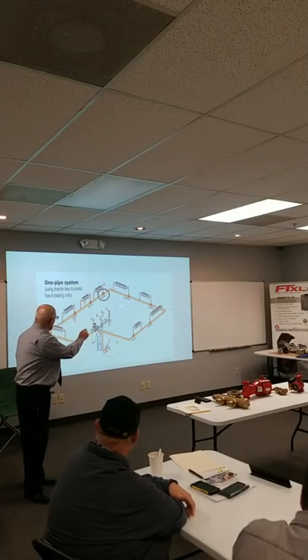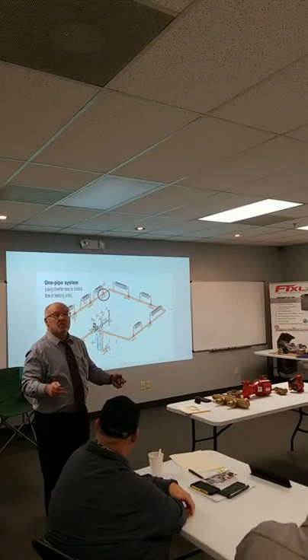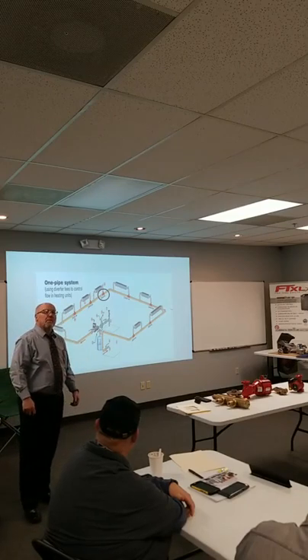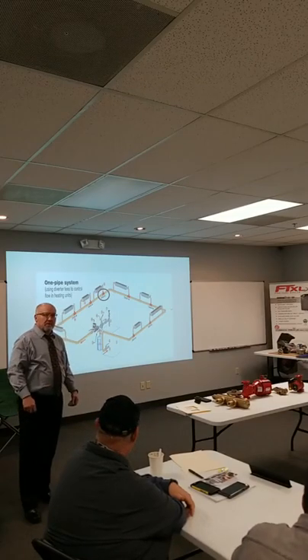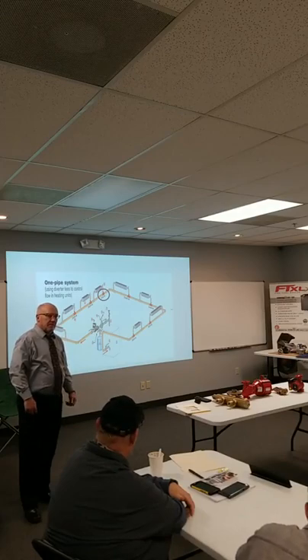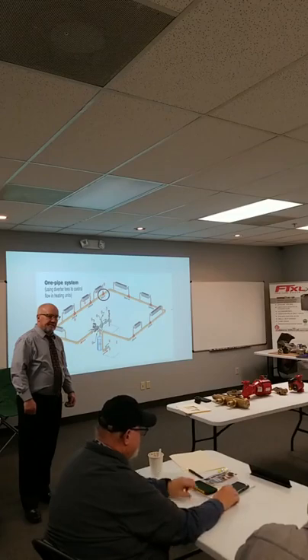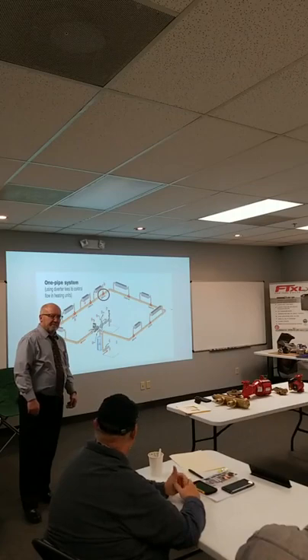Steve: If I had radiation going down, I might have two monoflow tees in that, supply and a return. I built a vacuum system for a steam job with a monoflow tee. Moving ten gallons a minute through a three-quarter pipe, plastic pump, we're drawing out of that branch, we were sucking 45 inches of water. Wow. Okay, so the way this works is amazing when you think about it. You're forcing water through the main part of the tee, you're sucking the water back through the branch.